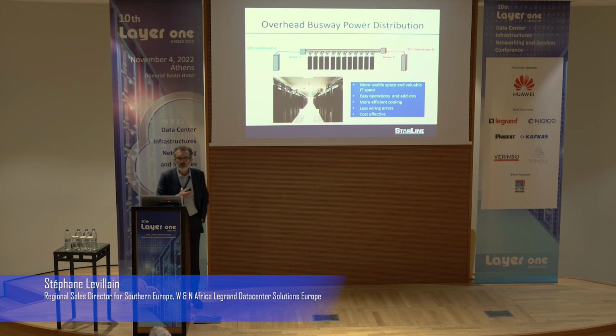And then it comes to this new kind of design. We get rid of the PDU cabinet. We get rid of the cables. We have only busway, end feed, and tap off on top of the racks to feed the racks with a feed B in red and a feed A in blue. You have more space. You can reuse the space of the PDU cabinet to install more IT racks, which gives more revenue for a colocation company, for instance. It's more efficient. It's more agile.